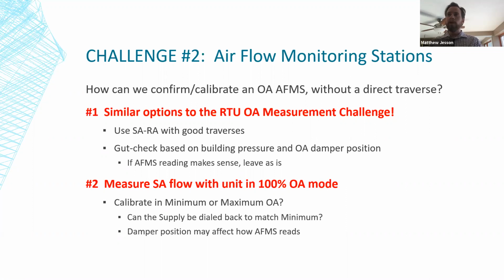So if you're going to calibrate it in minimum outdoor air mode, the one limitation might be whether you can dial back the supply enough to match that minimum. Because again, what we're talking about is closing off the return air and putting all our airflow through the outdoor air damper, and then your supply air reading should match your outdoor air damper reading, provided that there's no leakage or other air getting introduced somehow. So in some cases, if your minimum is pretty low, it might be difficult to dial back the supply or to get an accurate reading at a really low speed.